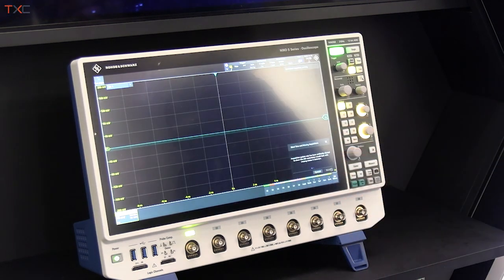This is how the instrument looks when all 8 channels are in use. Another interesting feature is 4 spectrums simultaneously. The MXO5 can process multiple spectrums, each with different settings, independent of the time domain while maintaining fast performance. Here you can see the 4 different spectrums simultaneously with different settings.